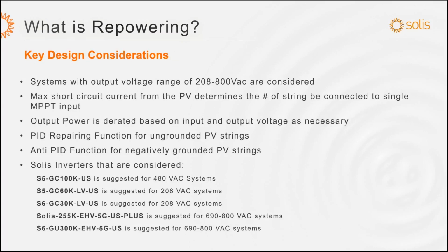Key considerations when doing repowering. The way we evaluate repowering projects is based on the output voltage range. So we look at what voltage of output is required. Is it 208 to 800? We can consider those voltages and those inverters to be repowered with our inverters. The main reason for that is to keep the interconnection the same. The purpose here is not to change the transformers or touch any of the switchgear, so we try to keep the interconnection or AC voltage the same.